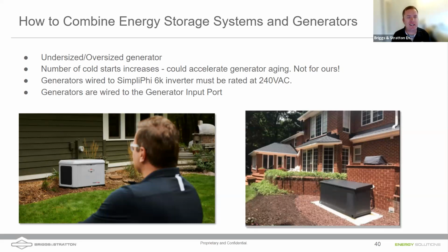Don't oversize it. Now, that's not going to be a bad thing, but what I'm trying to say here is that if you have a 26K generator, and like I just told you, you can only feed 9,600 watts into the inverter, you're going to have a generator that's running at a low load point, and you're not going to be running as efficiently as possible. There may be other ways, and it's possible to utilize some of that excess power when needed.